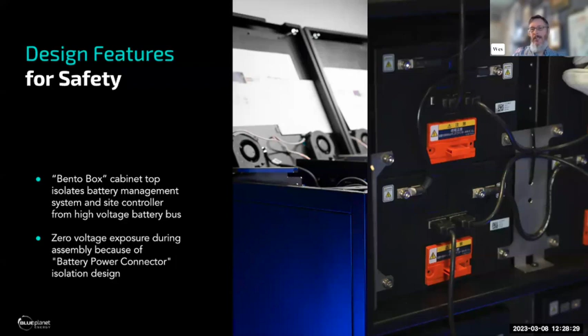The other photo shows what's inside if you open the enclosure, you'll see the batteries, and you'll see this bright orange box. This is a physical plug that's pulled out when the batteries are shipped and installed. When that plug is pulled out, the battery terminals read 0 volts, so you're just moving inert, safe boxes into the enclosures. You do all your wiring, both electrical and communications, which is all included. Then once you've built out the battery enclosure, you put in the battery plugs, and now you have 800 volts, which is a lethal voltage. So we keep safety in mind, not just in the battery chemistry, but in how we design the product to be used and installed.